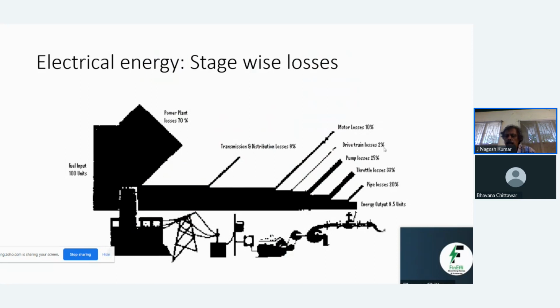If there is a pulley, chain, or belt, up to 2% loss will be there. Then it drives a pump, with pump efficiency at 75%, so 25% loss in the pump. Then you find the water is too much, so you slightly close the valve, 33% is the loss incurred by closure of the valve. And then the friction losses in the pipe are 20%.